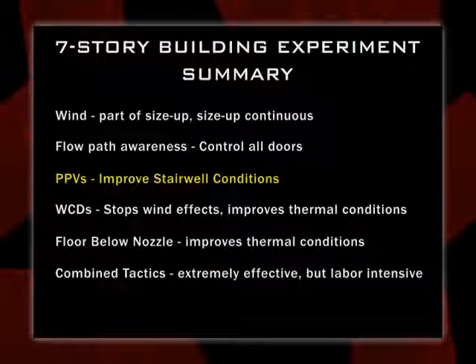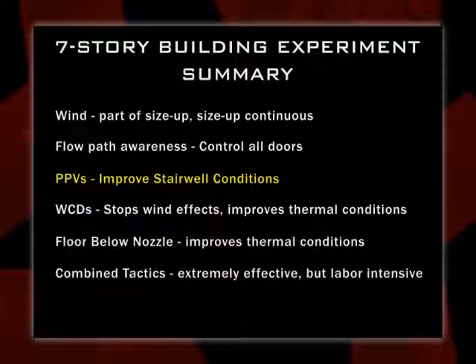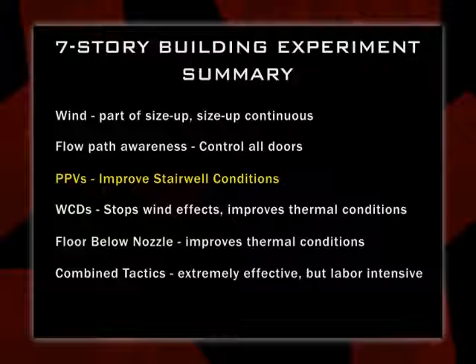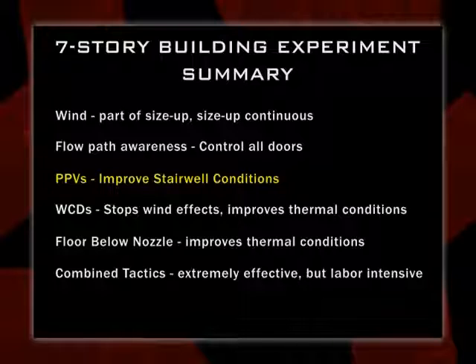It's always a good idea, or the common thought process is we're going to have an attack stairwell, we're going to have a ventilation stairwell, and no occupants are going to enter these stairwells, or we'll be able to keep all the doors shut and no smoke will get into the stairwell. We'll get all the occupants down, no problem. If anybody really gets that to work effectively and can keep the smoke from leaking around the doors into the stair shafts, that might be a viable option. Most of the time that doesn't happen. Using technologies such as pressurizing stairwells, which get used daily when buildings are engineered, can really help you out.